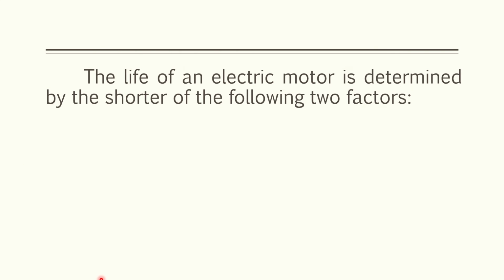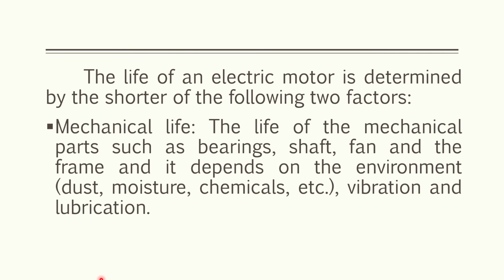The life of an electric motor is determined by the shorter of the following two factors. First, we have the mechanical life. The life of the mechanical parts such as bearings, shaft, fan, and the frame, and it depends on the environment such as dust, moisture, chemicals, etc., vibration, and lubrication. So this is one of the reasons why industries choose the TEFC type of electric motor, because TEFC designs prohibit the entrance of dust and moisture. And for that, it extends the mechanical life of the motor.